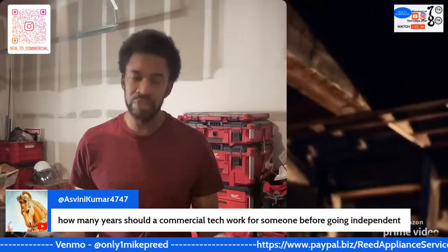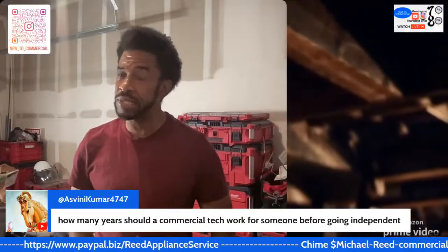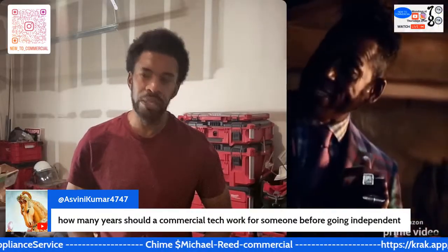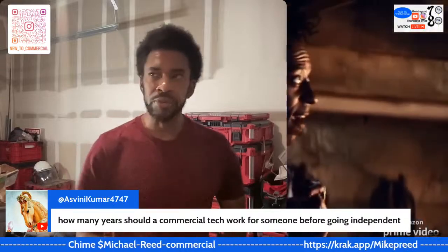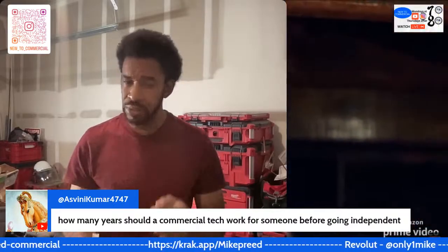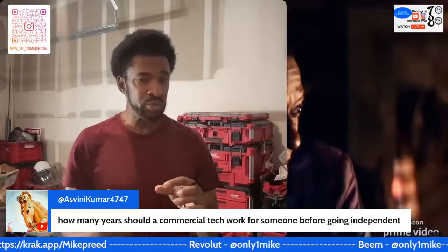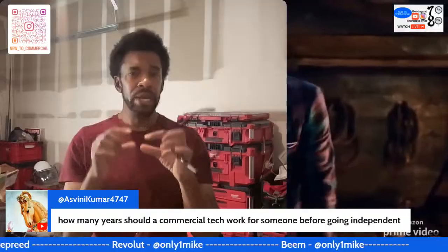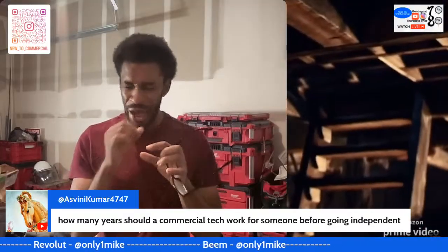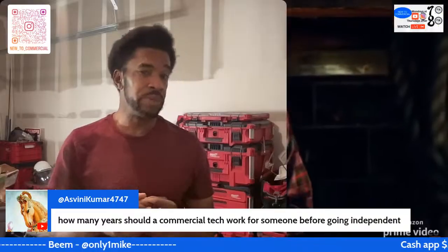There are some rules. You have to make sure the machine works. You have to make sure that it makes at least a batch of ice. We really don't have time to watch it make three. So the trick is to observe the ice that's already been made, and compare it with the ice that was just recently produced. If they are the same ice, there's a good chance the ice machine is going to be okay.